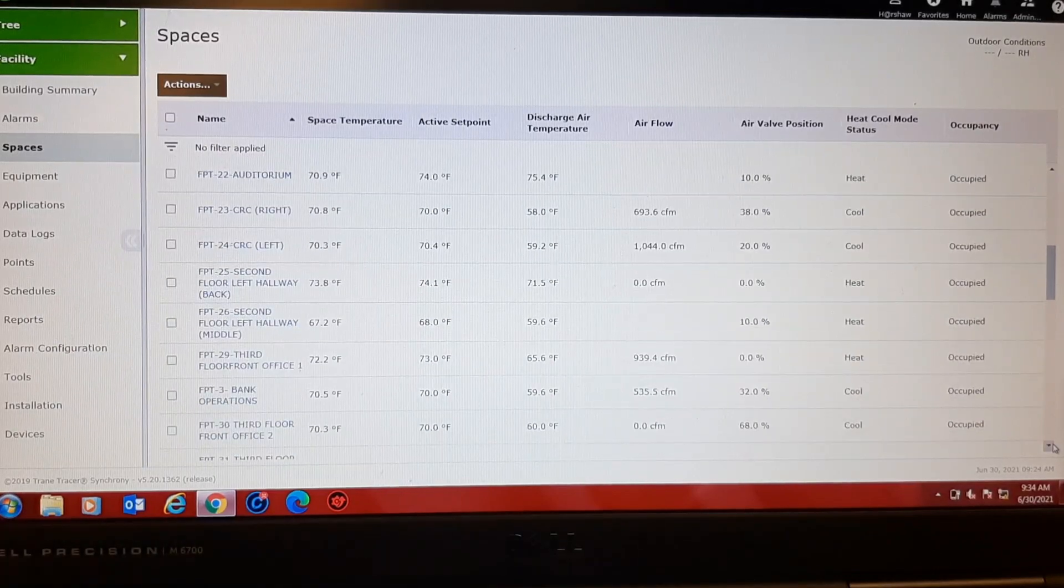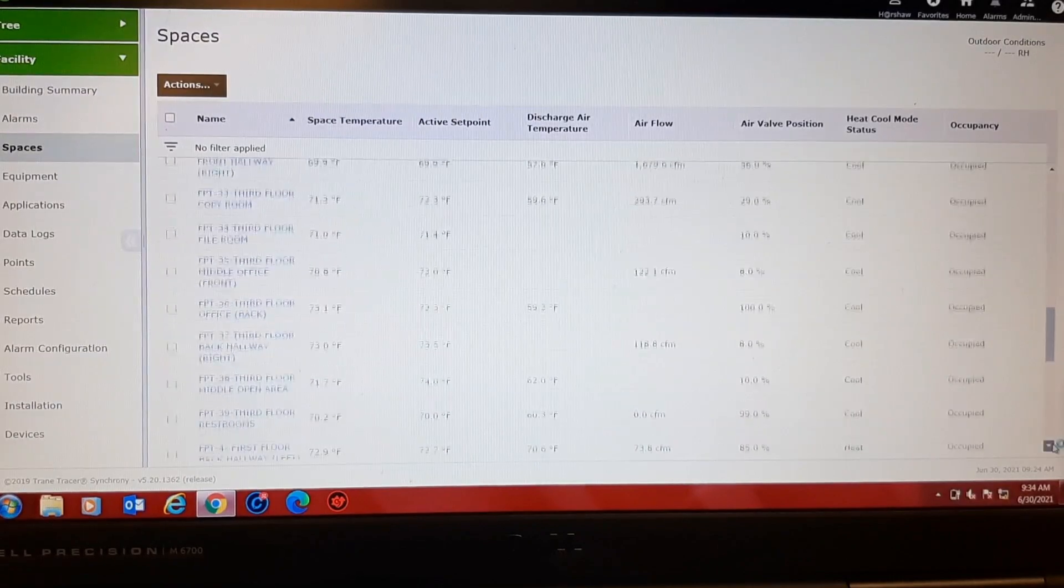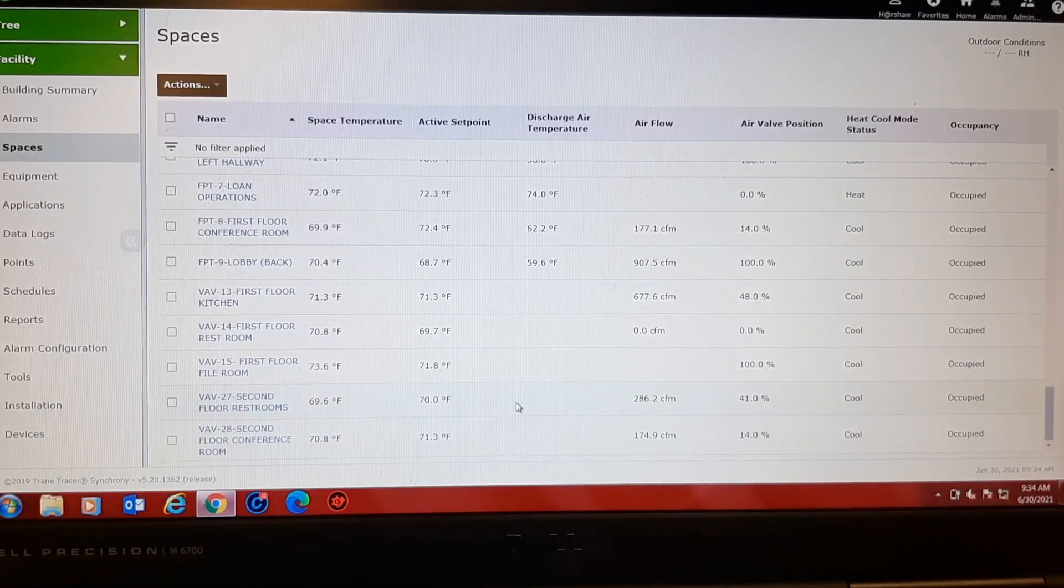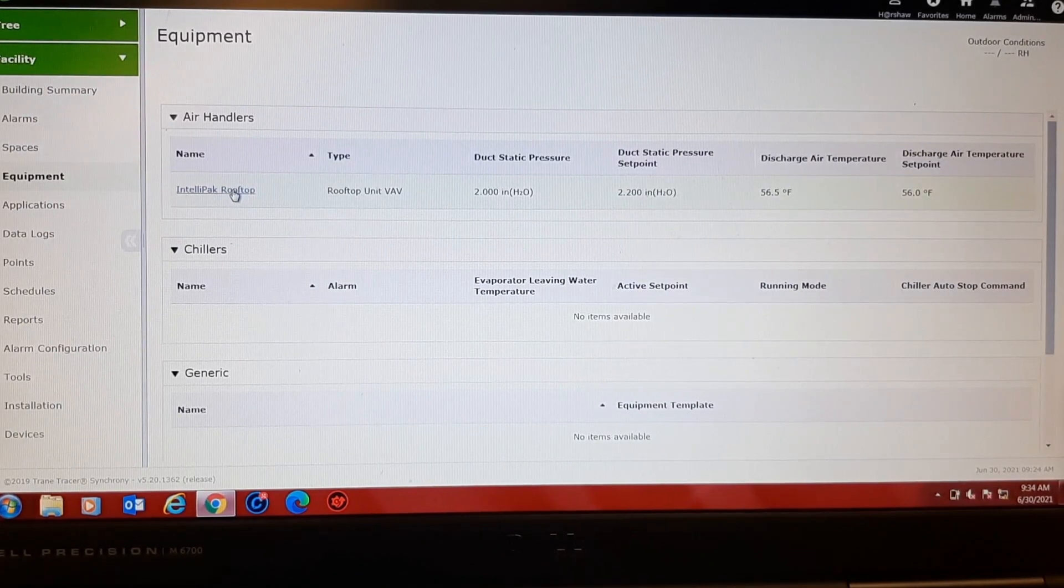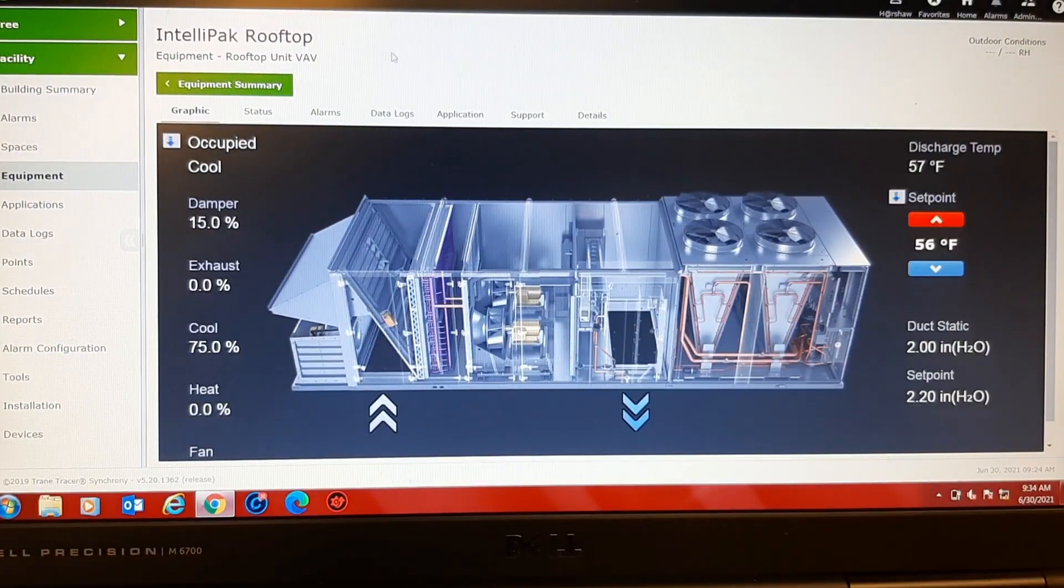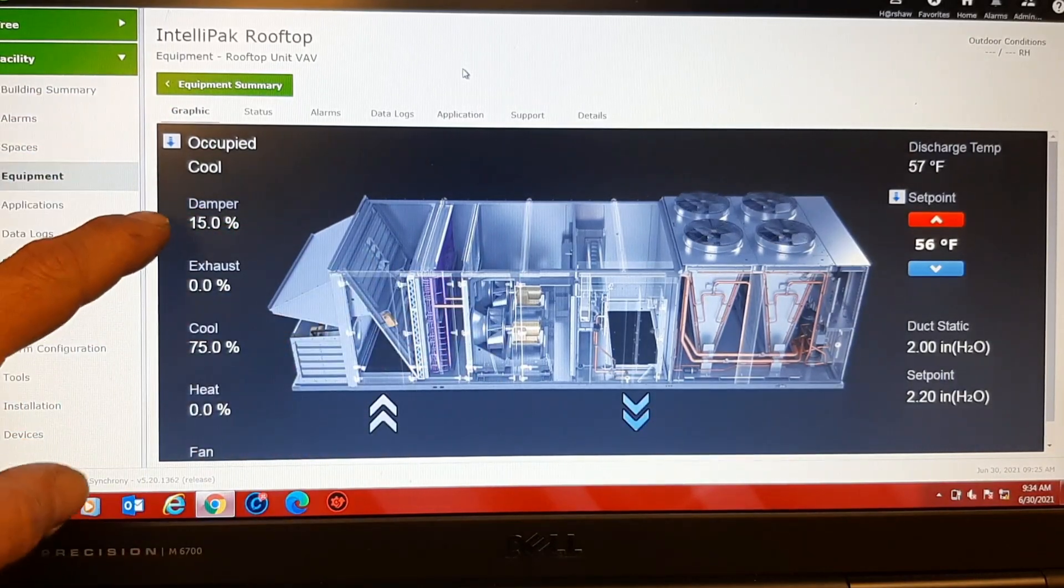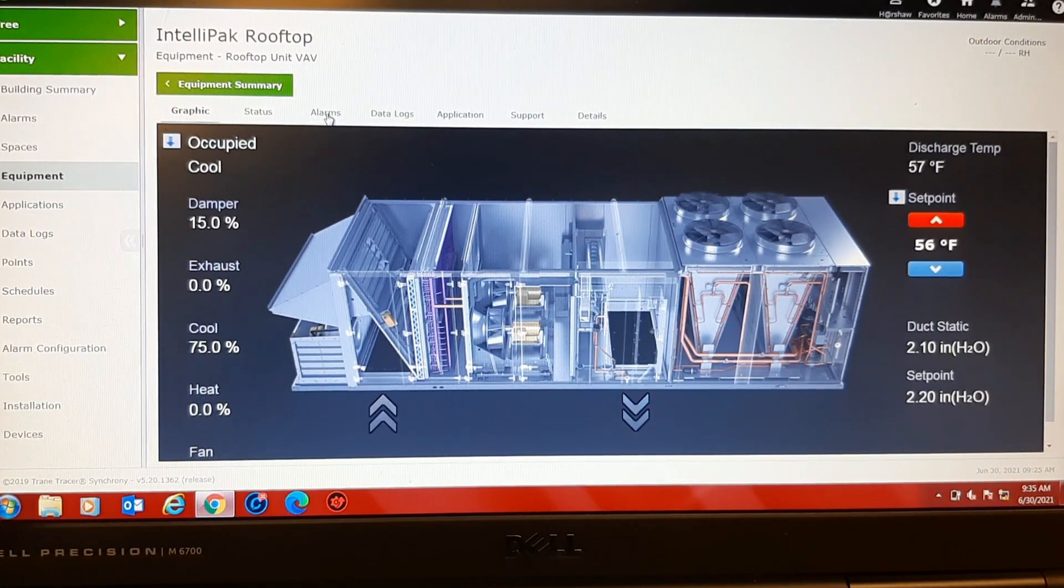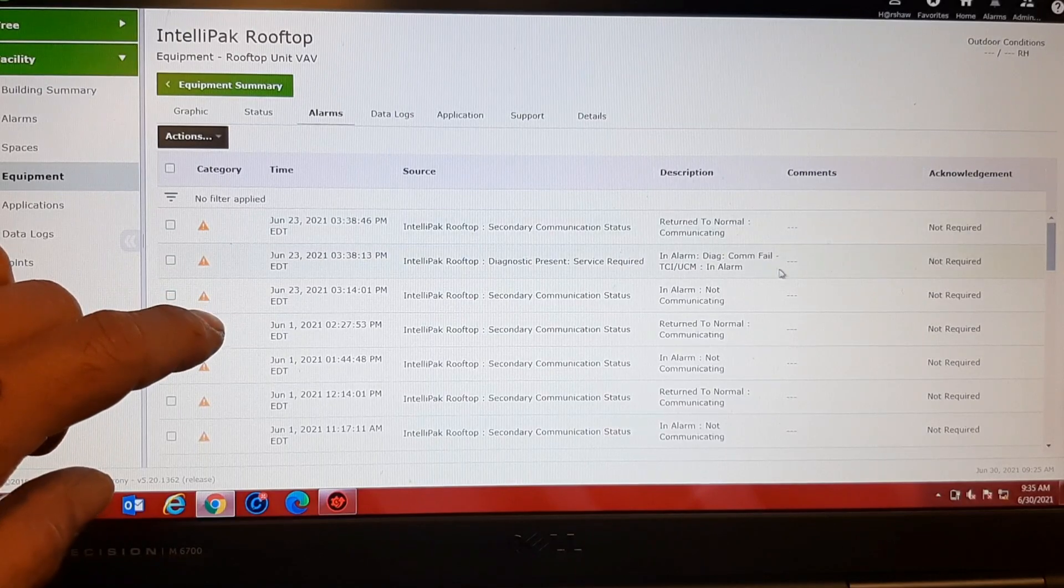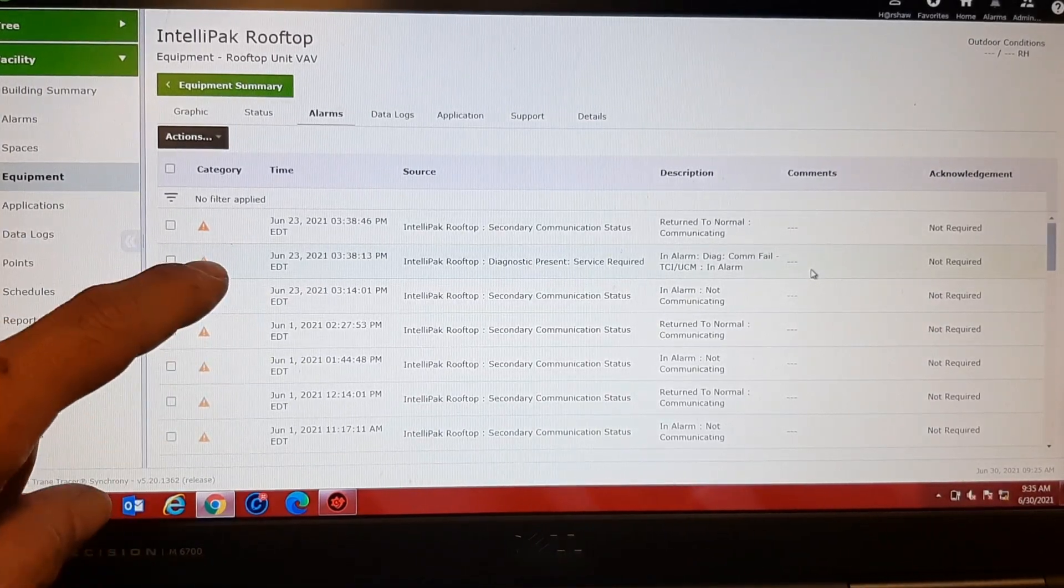These do have the Trane thumb wheel stats, so they're all going to be set all over the place depending on whatever anybody wants. There's a rooftop. 57. That's our min position on the economizer. Let's see if it shows any alarms.